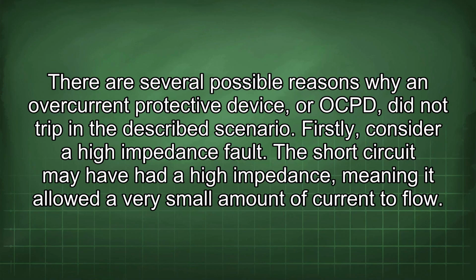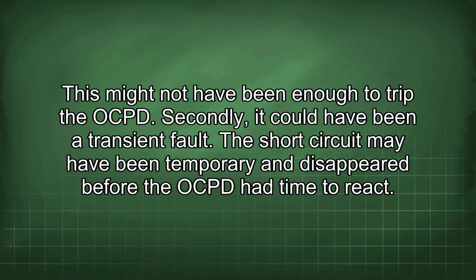There are several possible reasons why an overcurrent protective device, or OCPD, did not trip in the described scenario. Firstly, consider a high impedance fault. The short circuit may have had a high impedance, meaning it allowed a very small amount of current to flow. This might not have been enough to trip the OCPD. Secondly, it could have been a transient fault. The short circuit may have been temporary and disappeared before the OCPD had time to react.